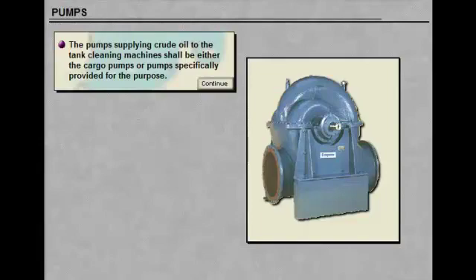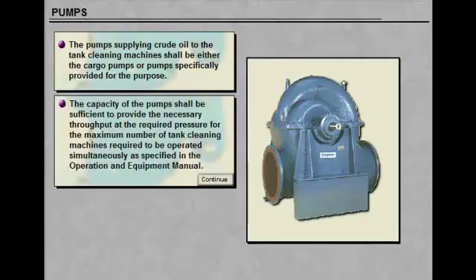The pumps supplying crude oil to the tank cleaning machines must either be the cargo pumps or pumps specifically provided for supplying crude oil to the tank cleaning machines. The capacity of the pumps must be sufficient to provide the necessary throughput at the required pressure for the maximum number of tank cleaning machines required to operate simultaneously as specified in the operation and equipment manual.